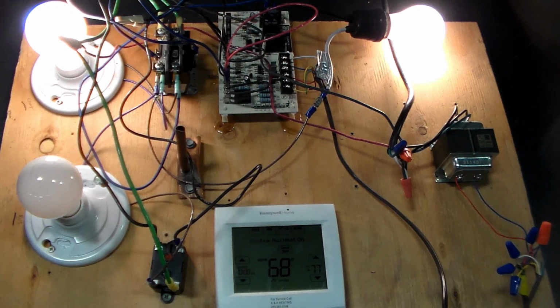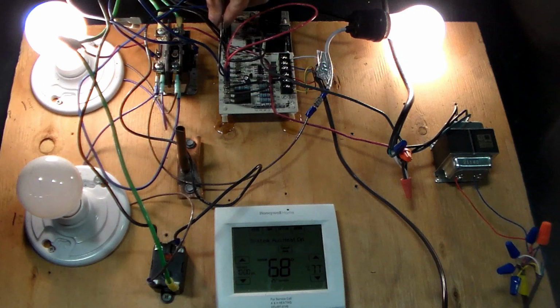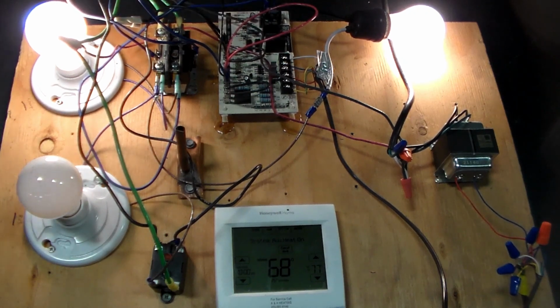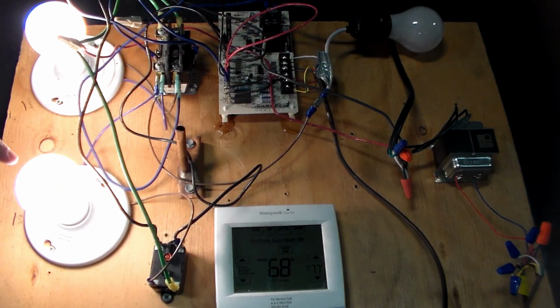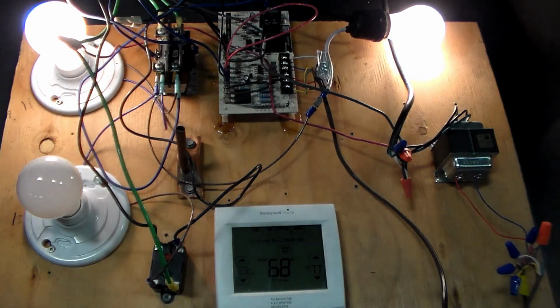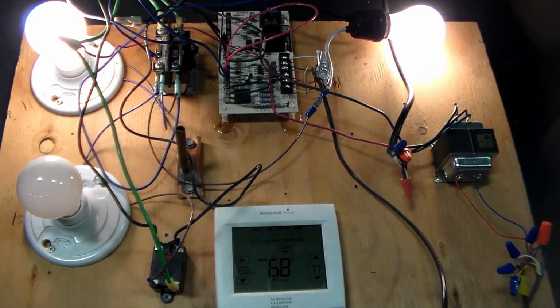So it could be not having power, and that's what happened in my house: the relay was stuck open. It wasn't sending power to the condenser fan at all, so I had to change the board out. And it was actually the fan going bad that took out the relay, arced out the relay and made it get stuck open. So weird things can happen, but if you test it and it shifts into defrost during test mode, reversing valve, you can hear it whoosh, your condenser fan goes off, then you've proven that the board is functional.